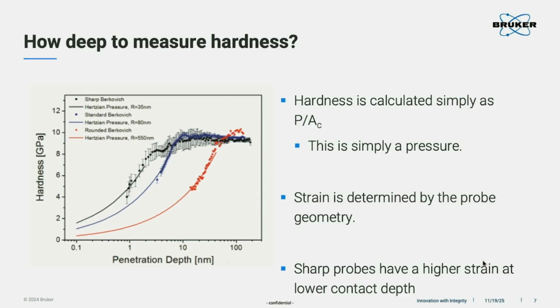So if we look at this, these are just 3 different probes. One is 35 nanometer radius, another one is 80, another one is much larger, more than 500 nanometer. This is the indentation data measured on the standard sample we call fused quartz. If we look at this, the quartz hardness is around 9 gigapascal, right? So before the plastic deformation, you cannot get the hardness value. This is the reason why you see the data going almost from the bottom to the stabilized zone.